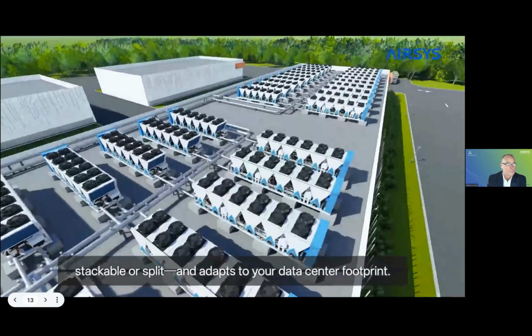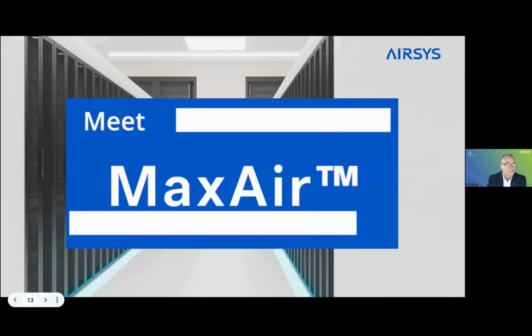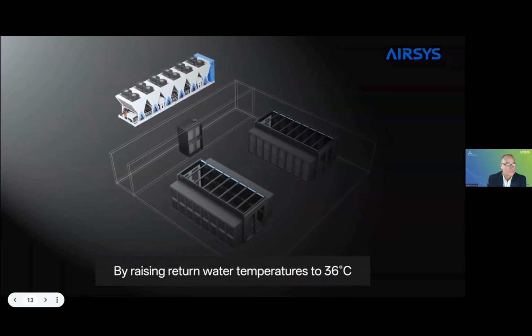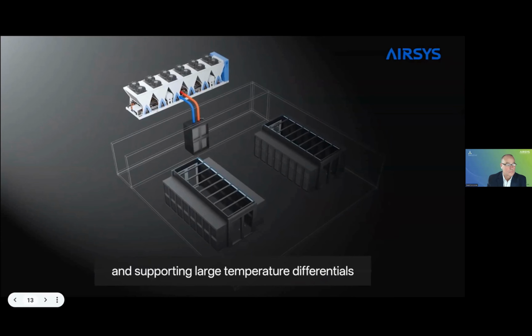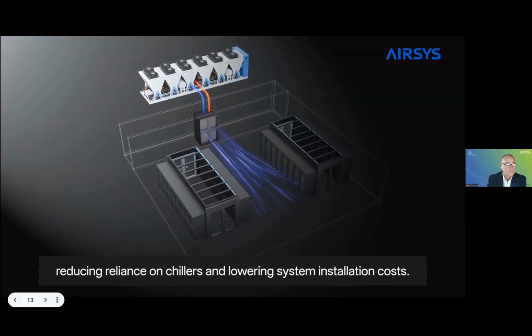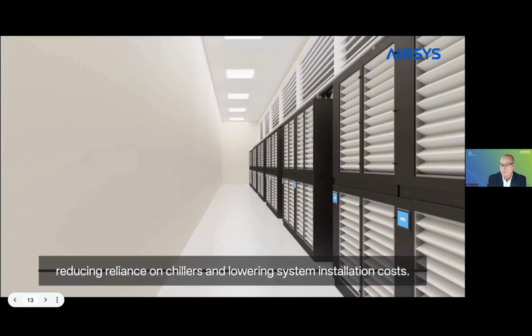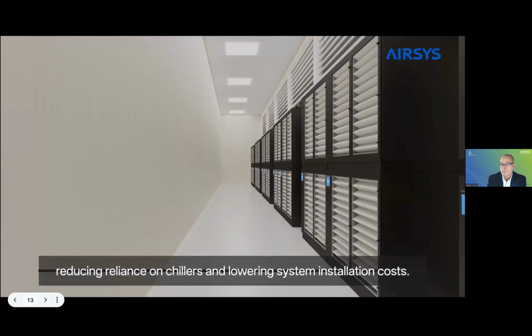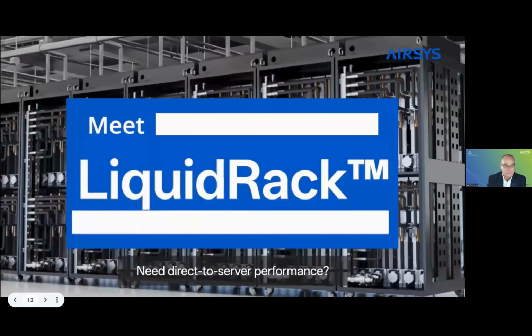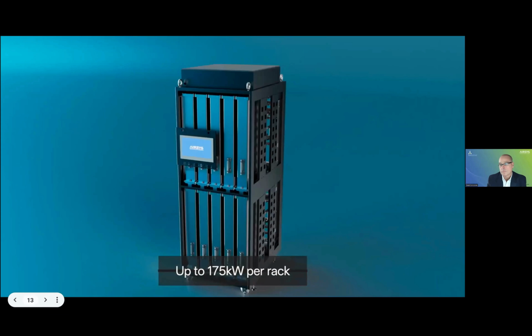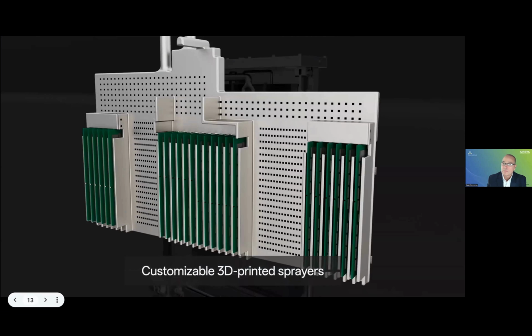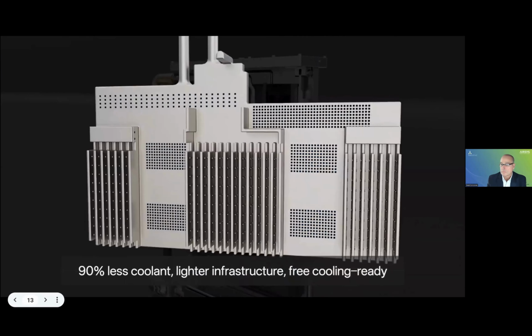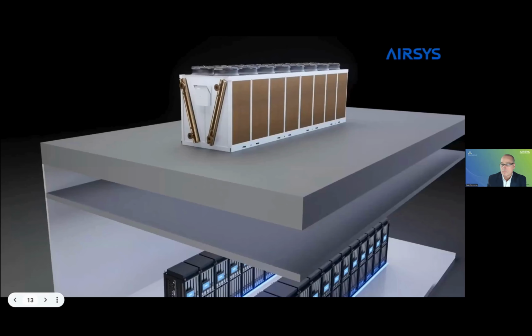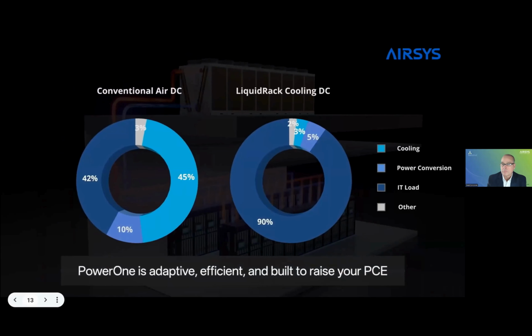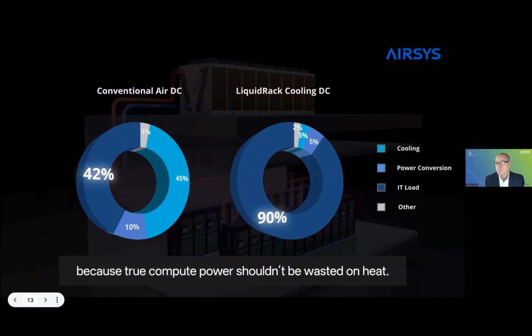For more free cooling, meet Maxer, our high-performance fan wall designed for high water temperatures and large delta T. By raising return water temperatures to 36 degrees Celsius and supporting large temperature differentials, Maxer enables the use of free cooling, reducing reliance on chillers and lowering system installation costs. Meet direct-to-server performance. Enter Liquid Rack, spray cooling at its smartest. Up to 175 kilowatts per rack. Customizable 3D printed sprayers. 90% less coolant, lighter infrastructure, free cooling ready. Power One is adaptive, efficient, and built to raise your PCE, because true compute power shouldn't be wasted on heat. Welcome to the new standard in data center cooling. Welcome to Power One.